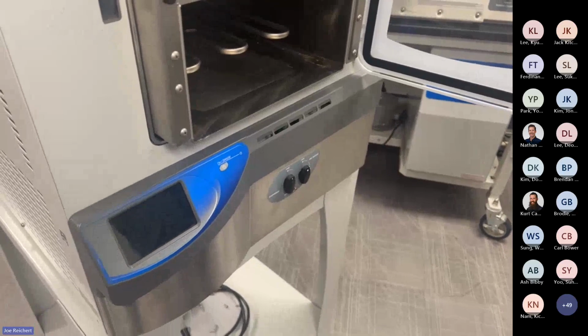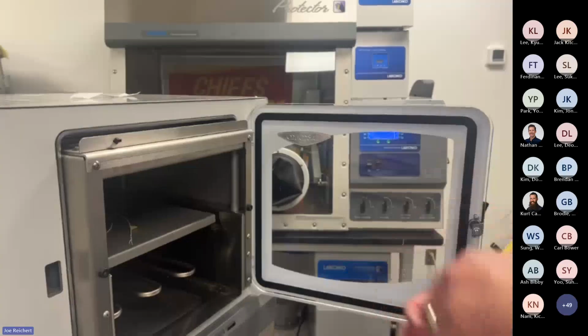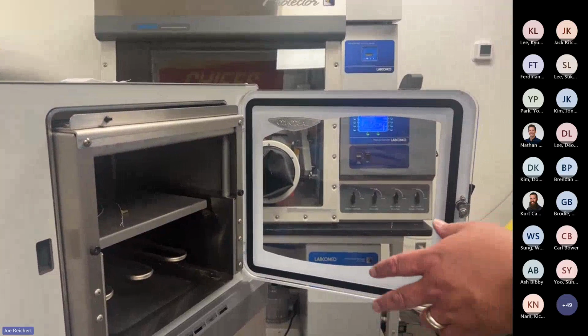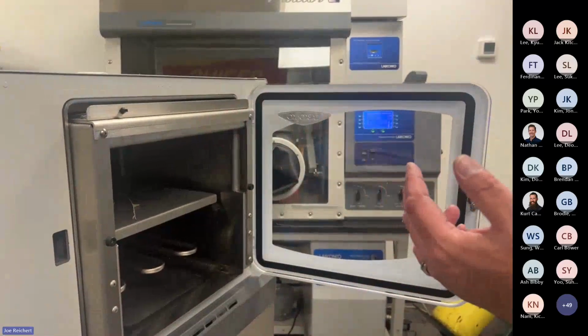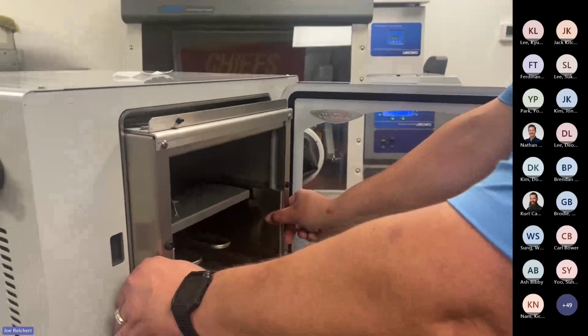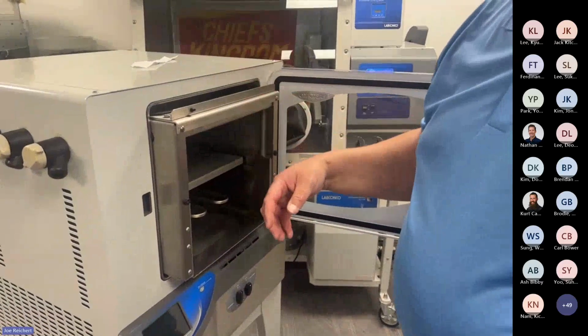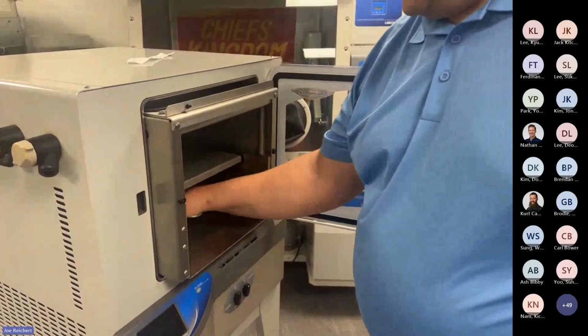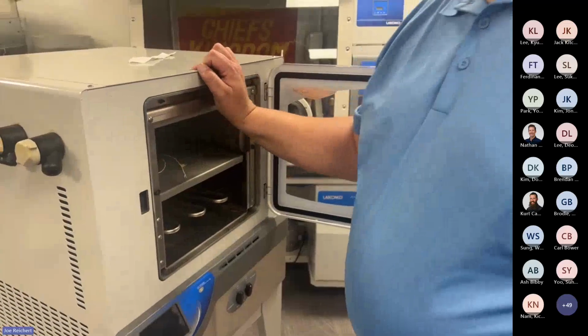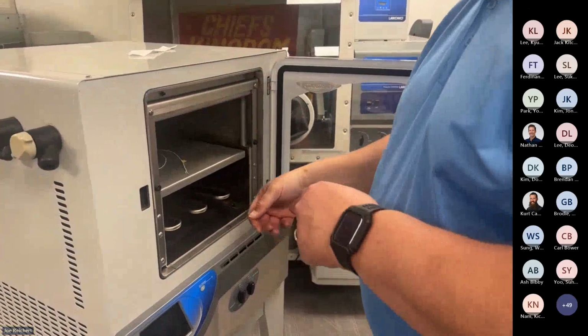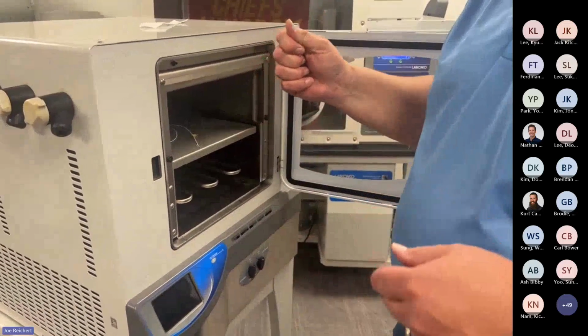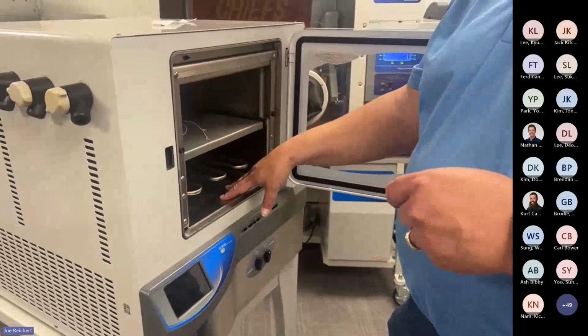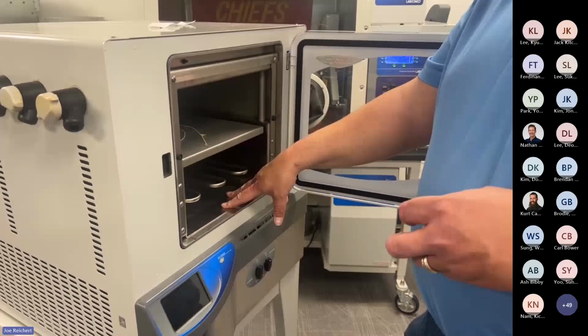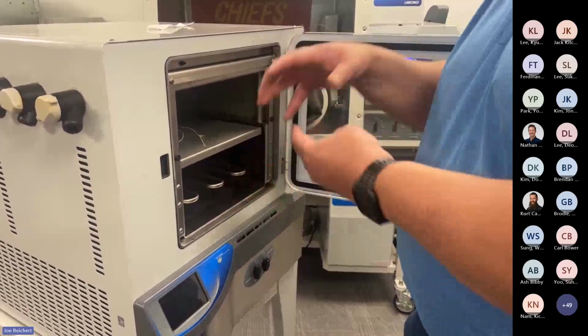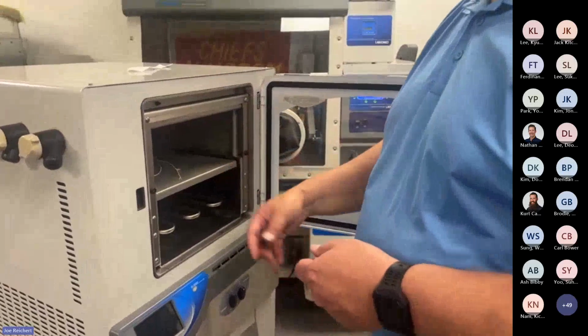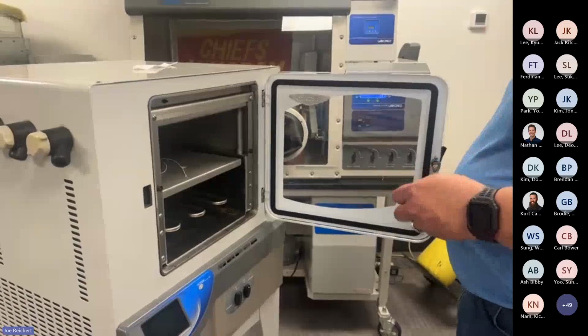If you have a unit where the bladder starts to open up and expand when you're not asking it to, then that means you have a leak someplace in the system, maybe in a valve, could be a pinched hose. Maybe the customer pulled out their stopping mechanism a little bit because a vial slid off in the back and they wanted to clean it. Maybe they broke some glass and they're trying to clean it out. Well, when they pushed it back in, they may have pinched that hose. So you might have to check to make sure that hose is straightened out, because if the hose gets kinked, then it's not going to be evacuated with the chamber when it's being pulled under vacuum. That ends up with two different pressures inside the bladder and inside the chamber. So the bladder will start to open up because it's not as low pressure as your chamber. So that's a sign that you have a hole or a kinked hose.